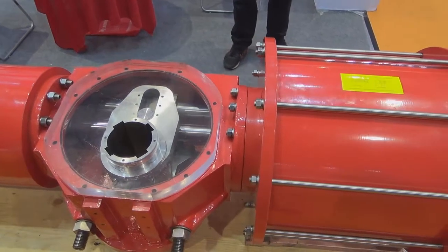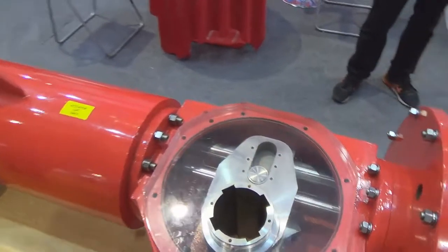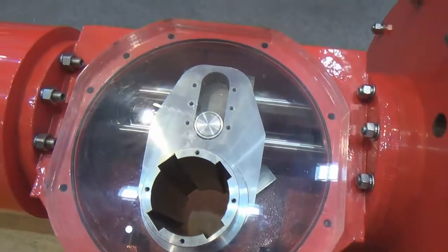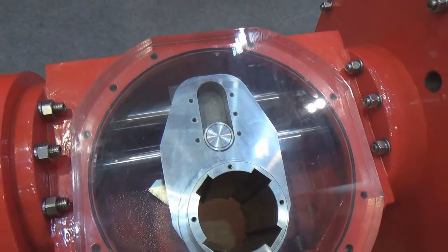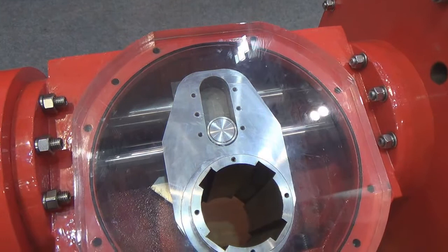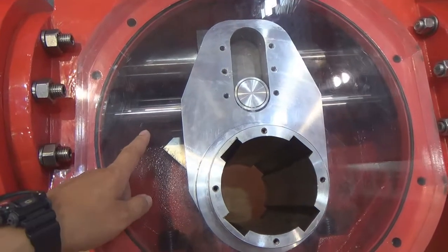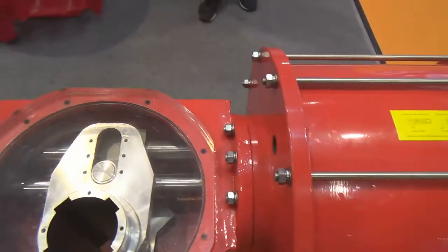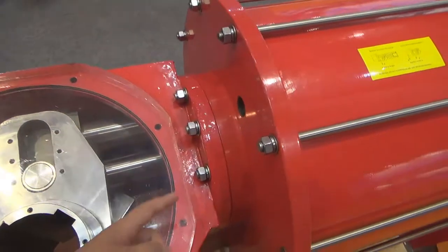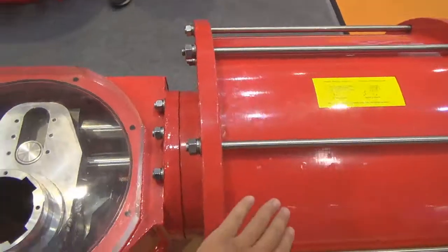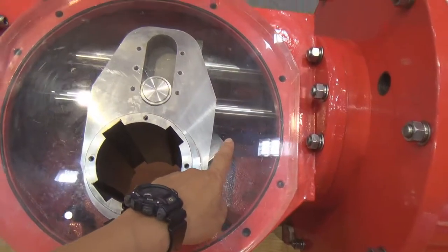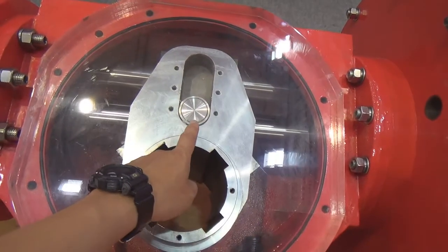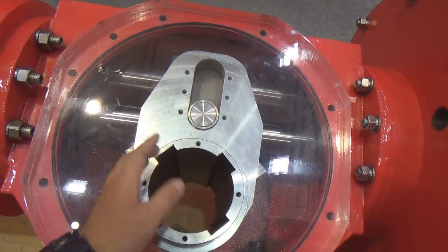Here is a very big pneumatic actuator. We can see inside to understand how the pneumatic actuator is going to work. The downside rod is connected with the spring and the piston. So when we put gas inside the piston, it pushes the downside rod.